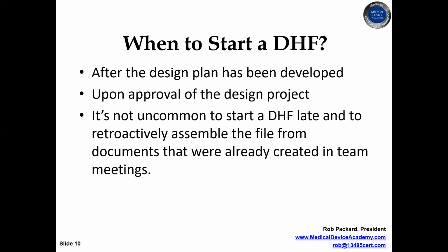When should you start the DHF? Well, I already covered that back in that diagram, but don't worry if your company is almost ready to submit a 510K and you don't have a DHF. The FDA is not going to come to inspect you until after your product is registered on the FDA website and you actually start shipping your product. So if you haven't shipped any product and you aren't registered with the FDA, they're not going to be looking at the DHF.